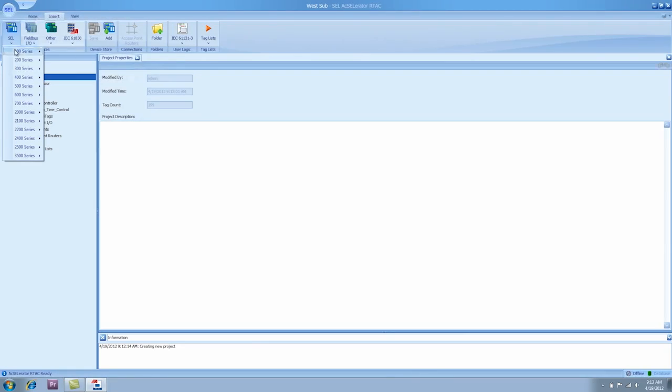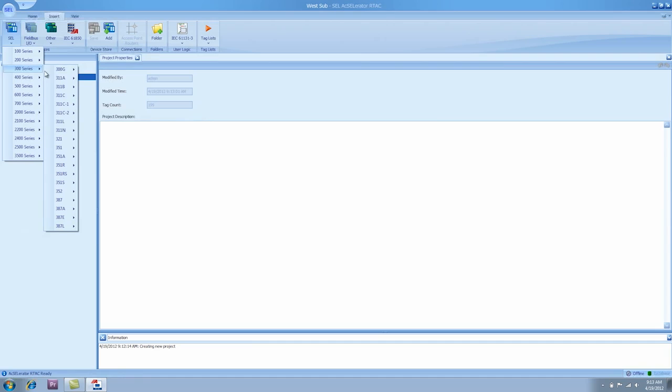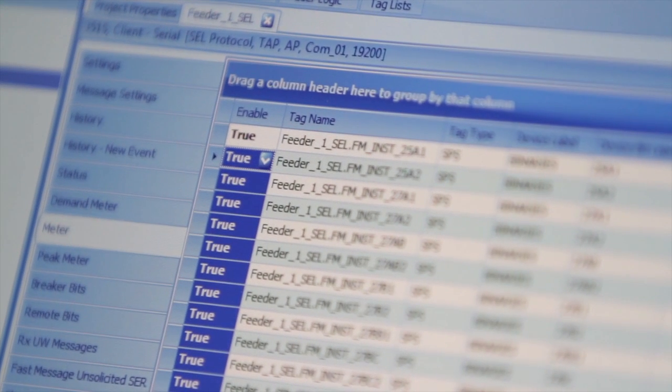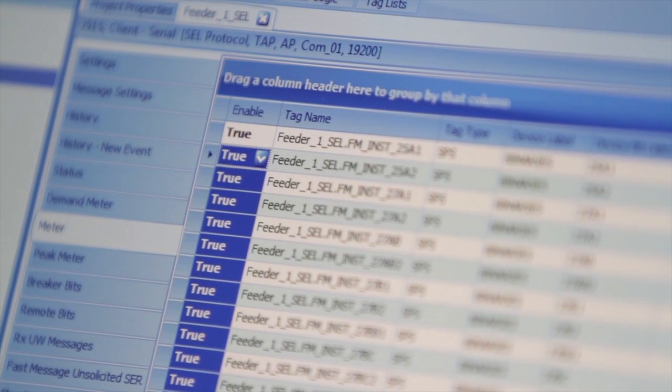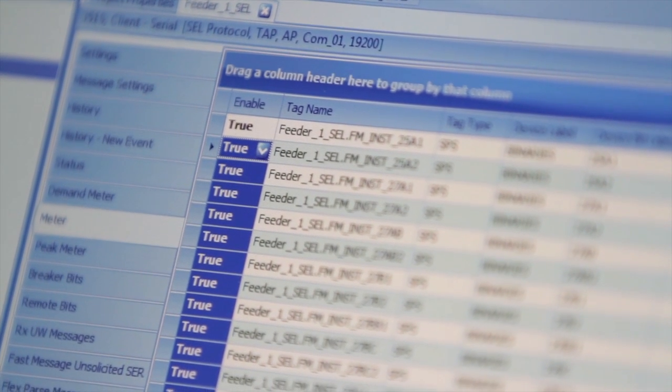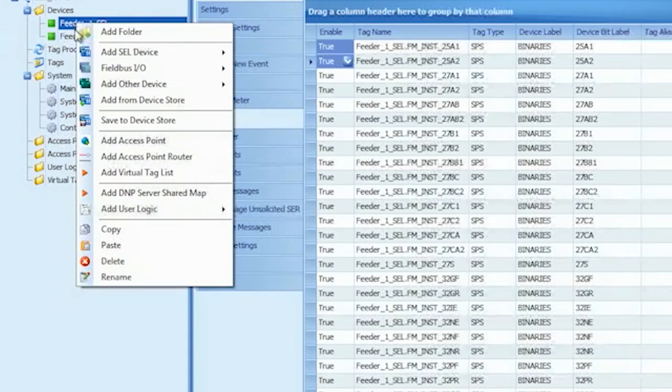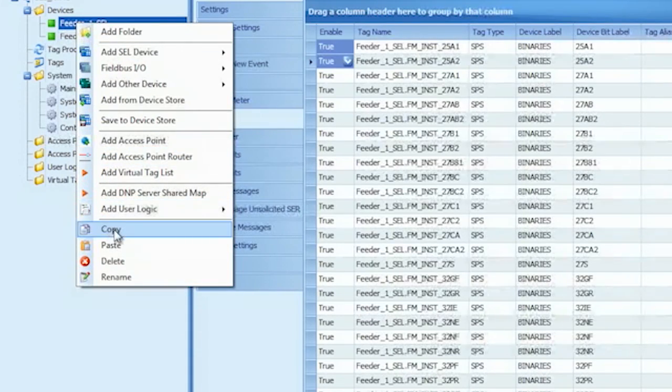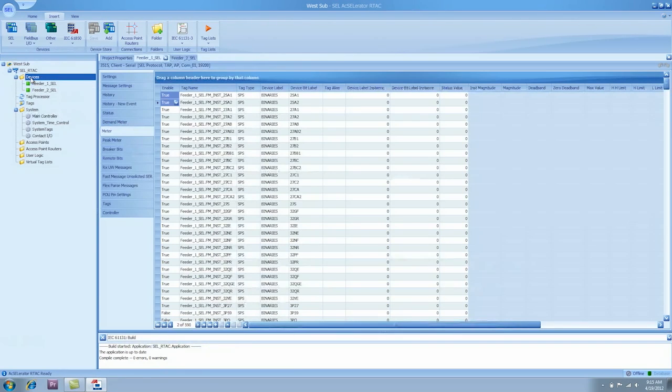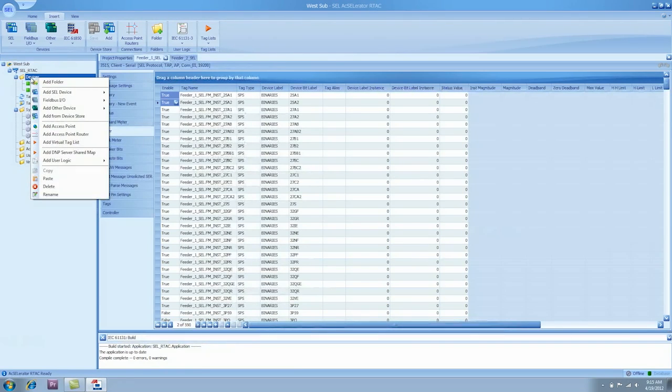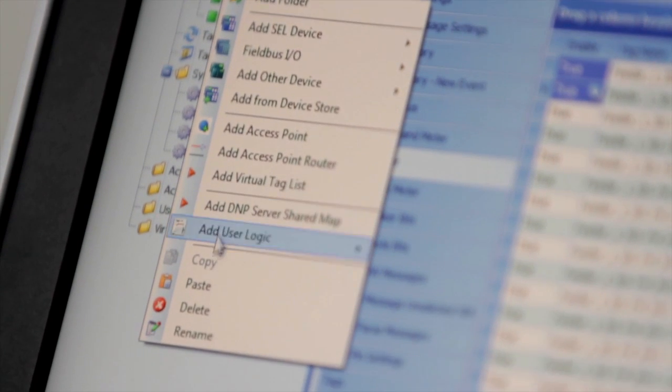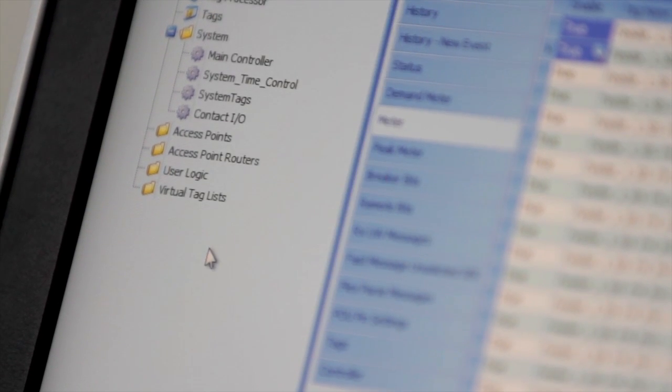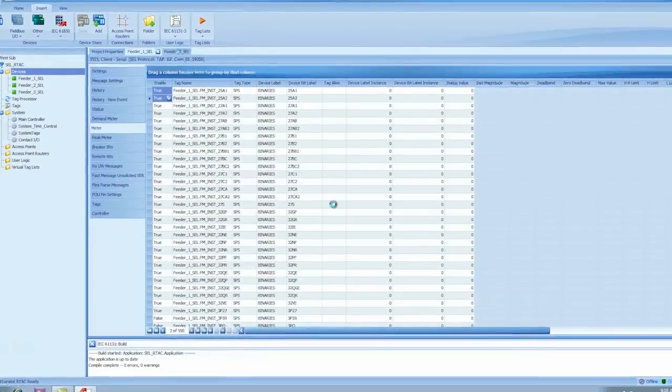Configuring a substation in the RTAC is really very simple. Select from the insert menu the device that you want. Say it's a 351S device. So you select that device, then select the protocol that the device will speak. Select the tags that you would like to retrieve from that device. Then you can copy and paste that device as many times as you want. If you have four feeders, and all four feeders are going to use the same relay, you can just copy and paste that device four times and you're good to go.